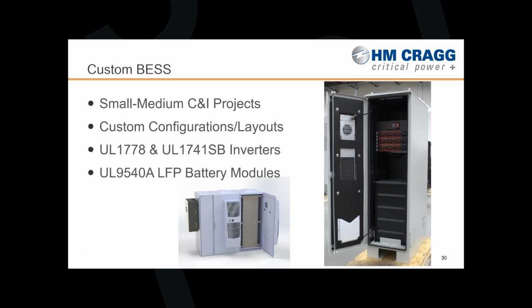The inverters we're using are UL listed under both the UPS certification, UL 1778, as well as the energy injection UL inverter certification, UL 1741 SB. This is powerful because we have a solution in the BESS world that can be applied into traditional UPS applications, but also has the ability to utilize distributed energy resources like solar, wind, hydro, and battery storage, and inject power back into the grid for a rebate from the utility company.